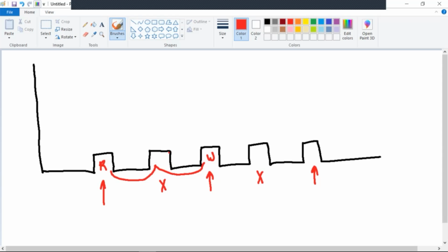What do I need to do from here to here? High pot. High pot. That is correct. I have to high pot this span, and I have to high pot this span before I can restore. Now, that's just the cost savings on fault indicators. That's all that is. I know we did that in some instances when we first started installing them. Then fault indicator prices came down, and we went transformer to transformer.